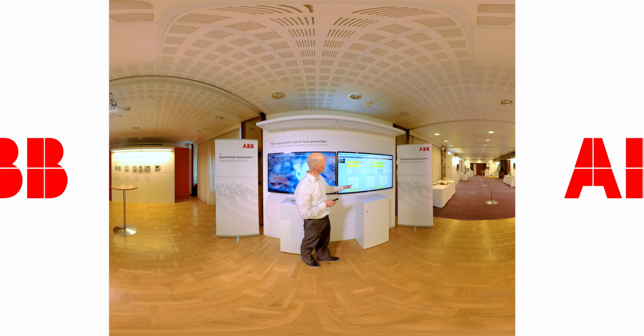So you can clearly see here that the phasors measured both in the faulty feeder and in the healthy feeders are greatly oscillating during the restriking earth fault. And it makes risks of tripping of the faulty feeder, as you can see here, marked with the red color. So this phasor marked with red does not stay permanently in the operate area. And similarly, there are risks of disconnecting the healthy feeder due to the fact that the phasor marked with green color does not stay in the non-operate sector.